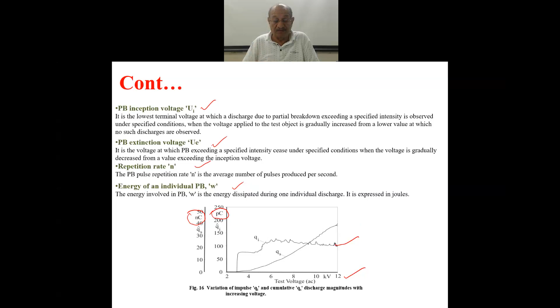So QI, after inception has taken place, retains a plateau, or the same intensity of discharge is taking place. When you increase the voltage, it may increase the repetition rate, but the intensity of discharge at the location would continue to be the same. Whereas when you increase the voltage, there may be more locations where the partial breakdown activity would start taking place. So the cumulative discharge intensity is proportional to the applied voltage. It increases with the application of higher voltage. So these are the two very important characteristics for QI and QS.